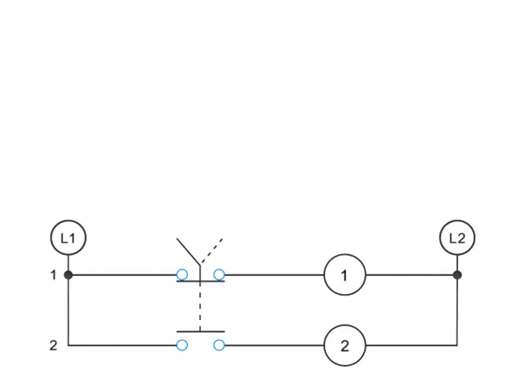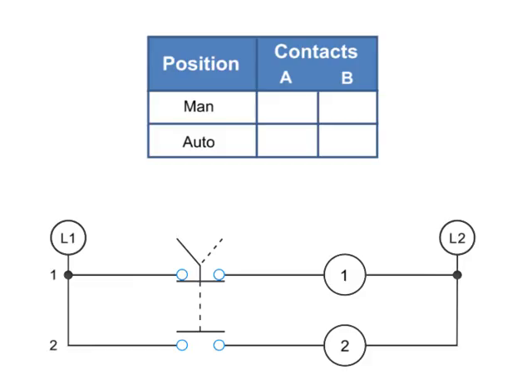Contact position on a selector switch can easily be illustrated using truth tables. This truth table illustrates the manual or automatic contact positions of a two-contact selector switch. Each contact on the line diagram is marked A or B. The positions of the selector switch are marked MAN for manual or AUTO for automatic. The truth table can be used to easily interpret what contacts are closed for a particular position.